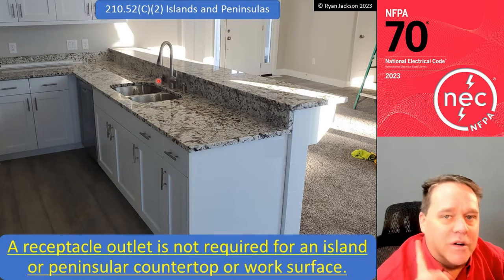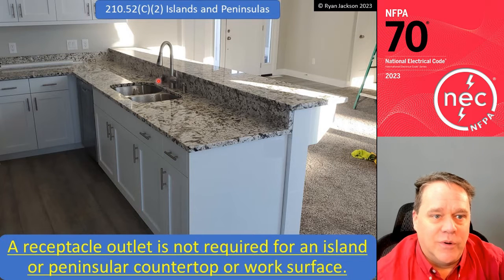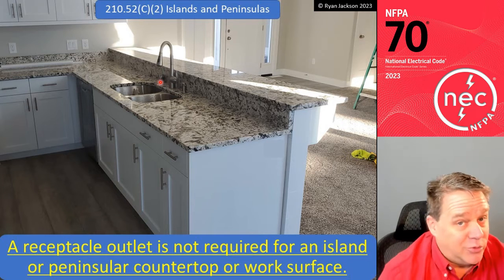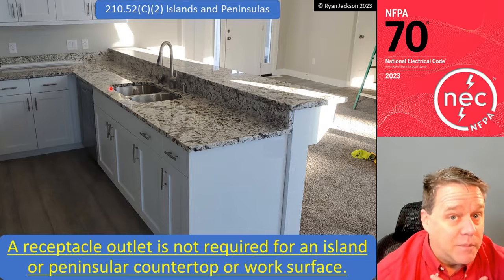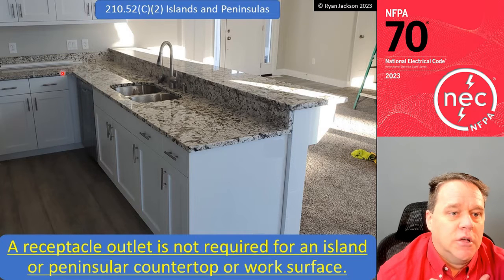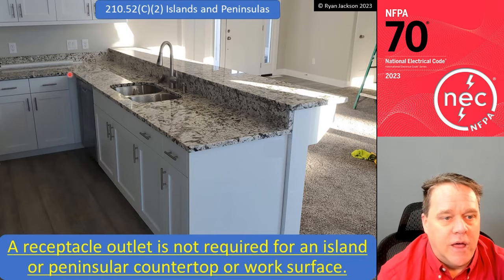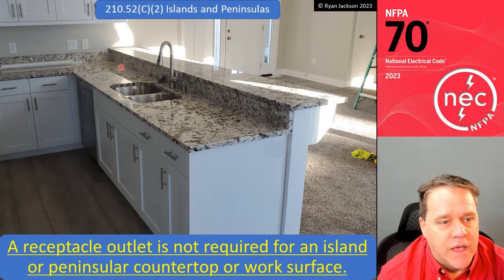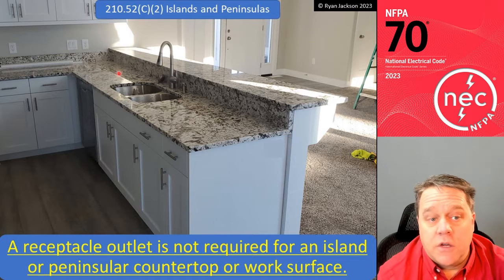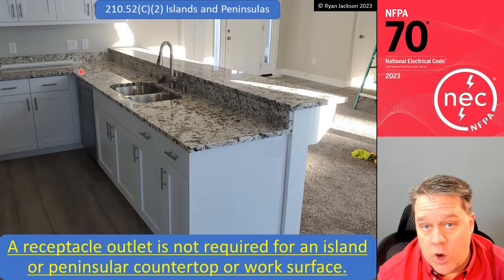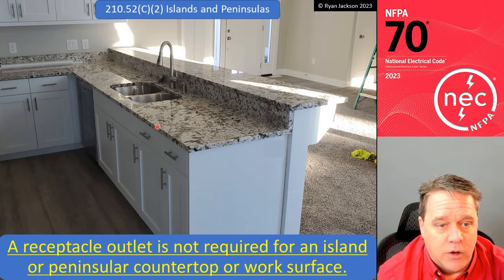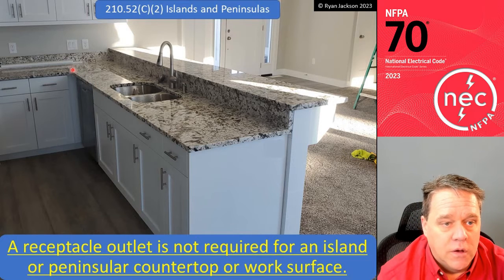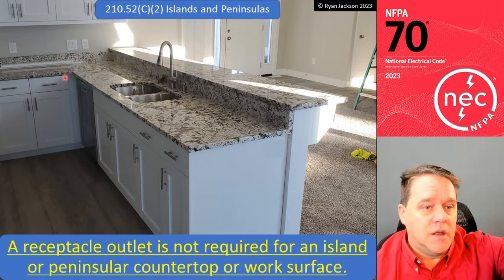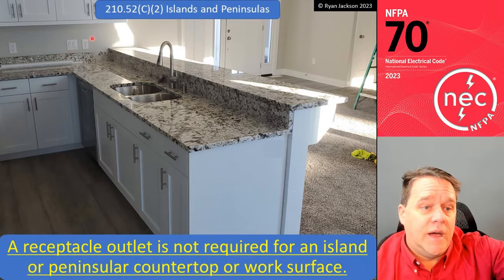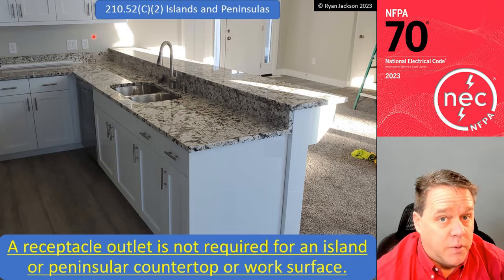Now, where does the peninsula begin and where does it end? Well, I don't really like the way the code says. In my opinion, the peninsula should start here at the connecting edge. But in the code, it says it's measured at the connecting wall, which means I would follow the edge of the countertop and extend an imaginary line. That switch and that receptacle are on the peninsula.